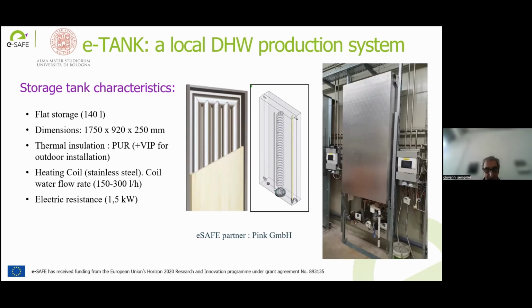The central pipe is equipped with a screwed flange and a heat exchanger, which is connected to a 2-pipe hot water network system powered by the central heat pump. The recommended flow rate within the heat exchanger ranges from 150 to 300 liters per hour. There is also an electric heater of about 1.5 kilowatts to ensure periodic high temperature for the prevention of Legionella disease. Standard thermal insulation is polyurethane rigid foam, but if we want to increase the insulation when the system is installed outdoors, it's possible to also add vacuum panels in order to increase the total thermal insulation of the system.